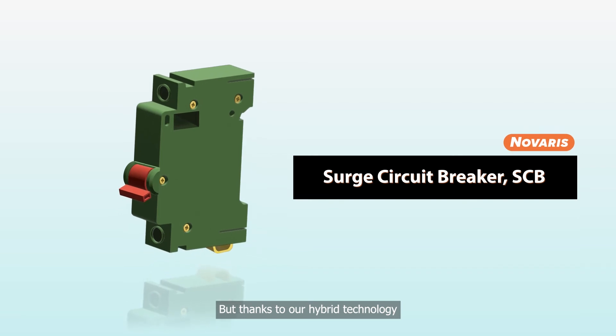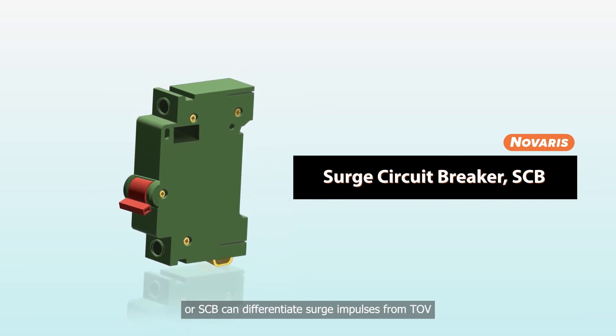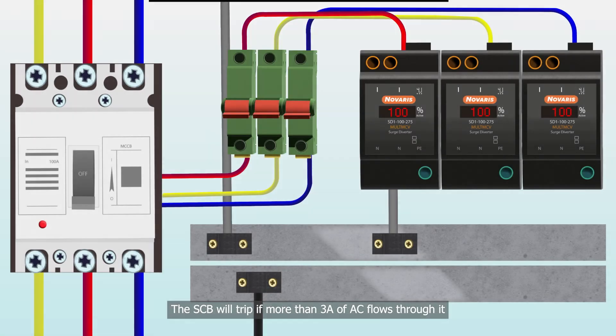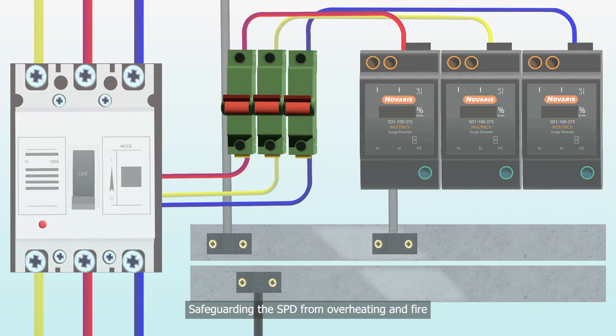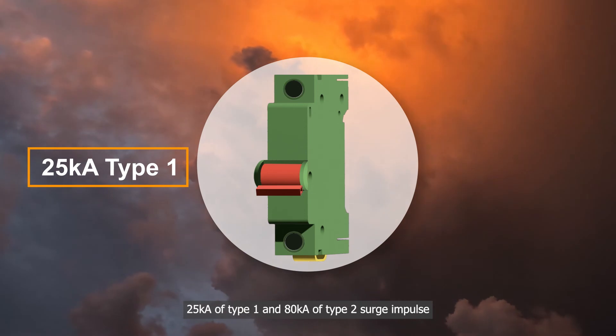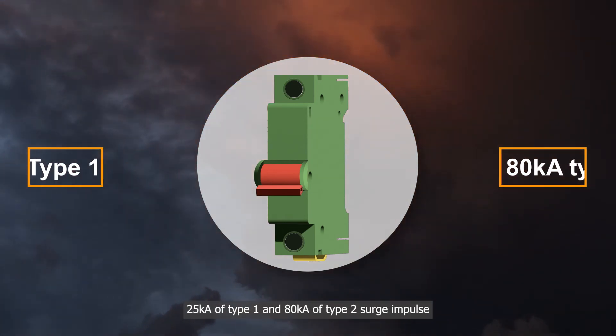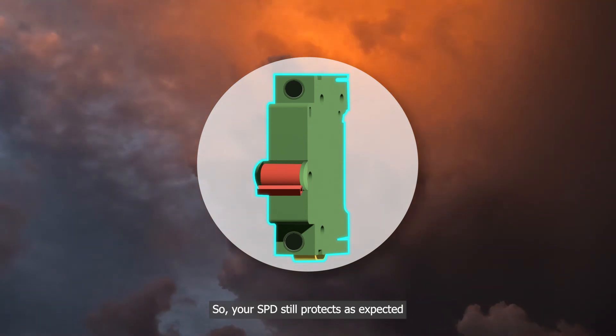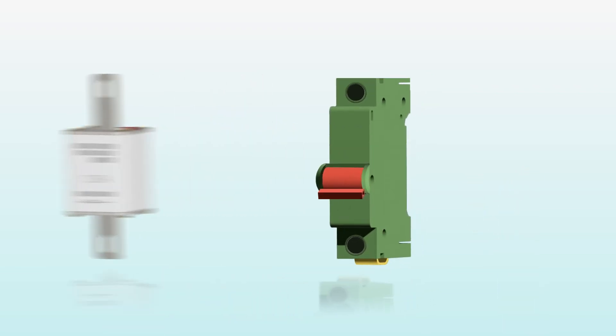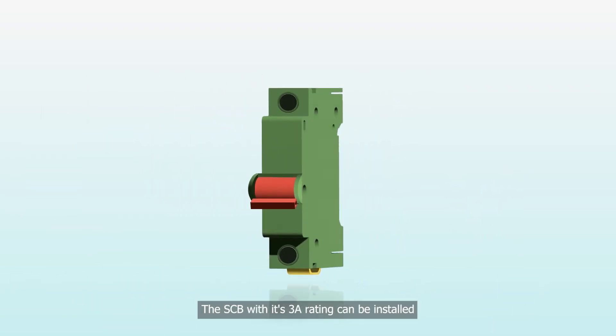But thanks to our hybrid technology, the Novaris Surge Circuit Breaker, or SCB, can differentiate surge impulses from TOV. The SCB will trip if more than 3A of AC flows through it, safeguarding the SPD from overheating and fire. It has a built-in surge element that can pass through up to 25kA of Type 1 and 80kA of Type 2 surge impulse, so your SPD still protects as expected. Installation only requires small conductors, since 3A is the maximum AC rating of the SCB. The SCB with its 3A rating can be installed in any switchboard and will still comply with the wiring rules.